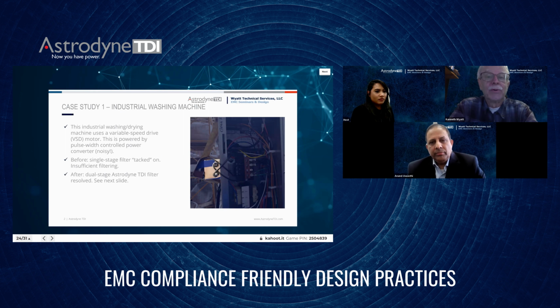So let's move on, we've got a couple of case studies to show you. This particular case study is an industrial washing machine. It turns out most appliances these days use what's called a variable speed drive motor. These motors are driven by a pulse width controlled power converter, which usually produces a very wide range of harmonic noise currents. In this case study, the client had tested a commercial washing machine and simply tacked on a line filter with poor attenuation properties. So I helped them select a more appropriate filter, and after comparing its performance with a dual stage filter from Astrodyne TDI, I supplied them a sample.